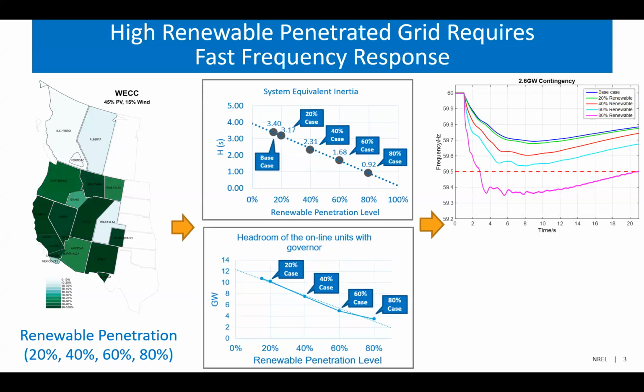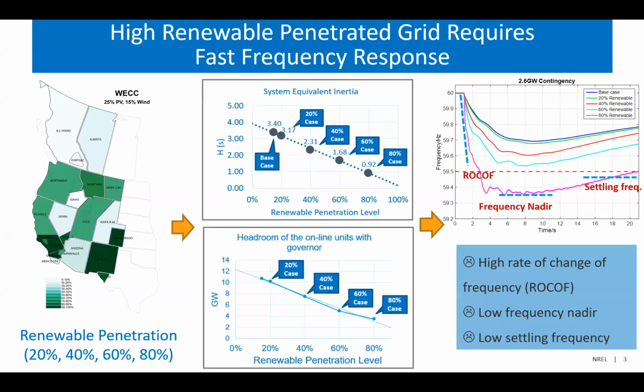So there is no doubt that it can lead to a much faster and deeper frequency drop during the event, especially for the 80% renewable penetration cases. The frequency nadir can even drop below the first stage of the under frequency load shedding. It implies that it has the potential to cause more outages or blackouts if we take no action. In fact, the industry has already taken action on it. For example, ERCOT has implemented the faster frequency reserve services to incentivize the load to provide those services.